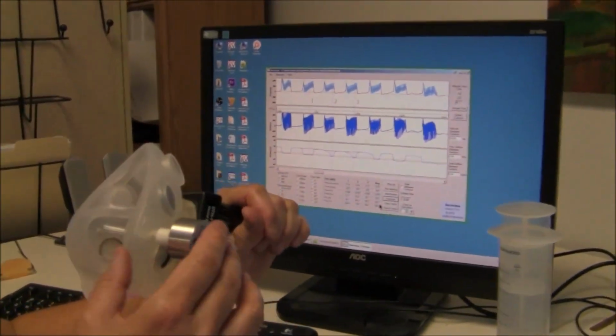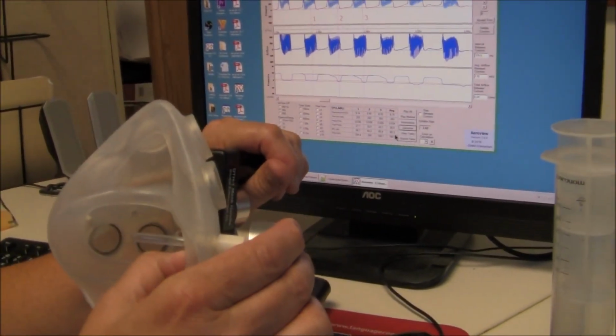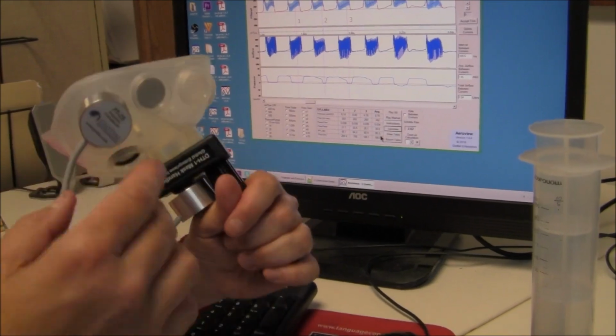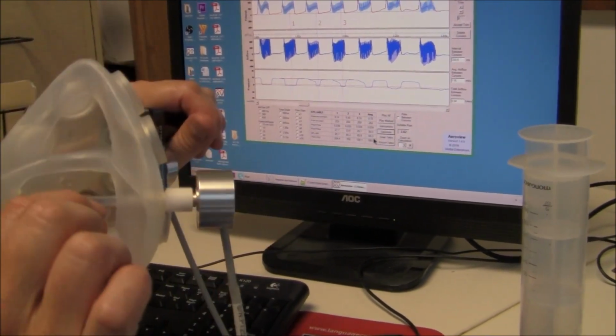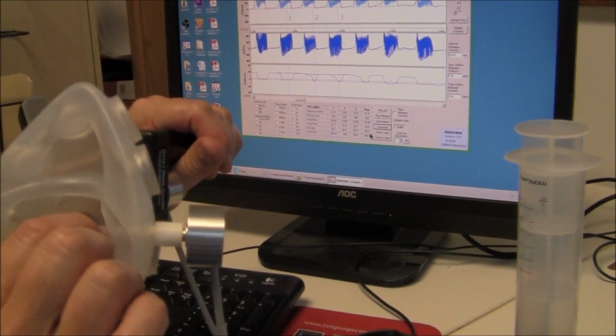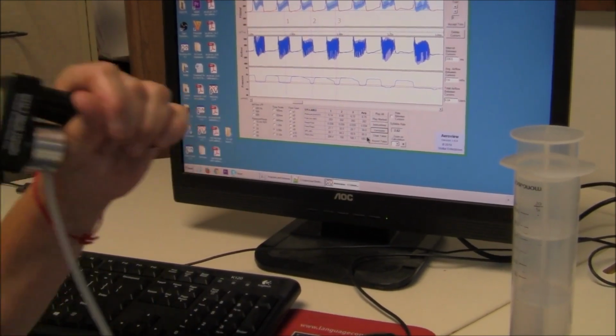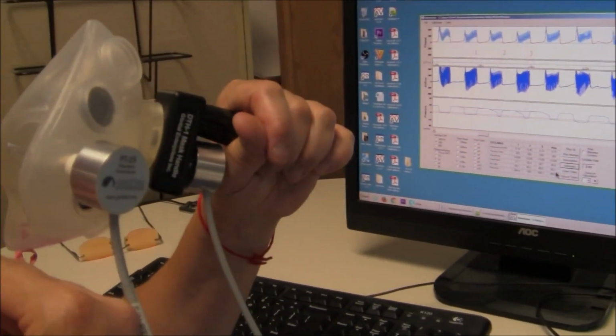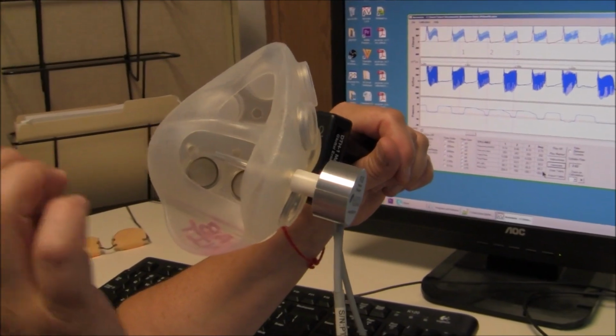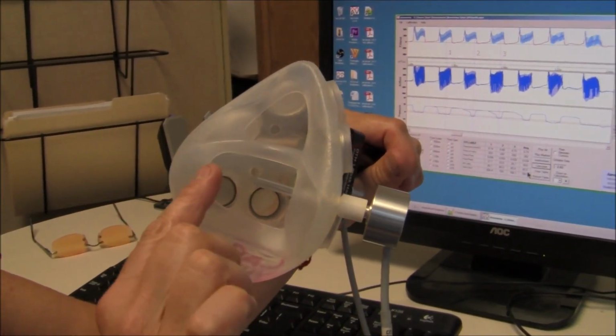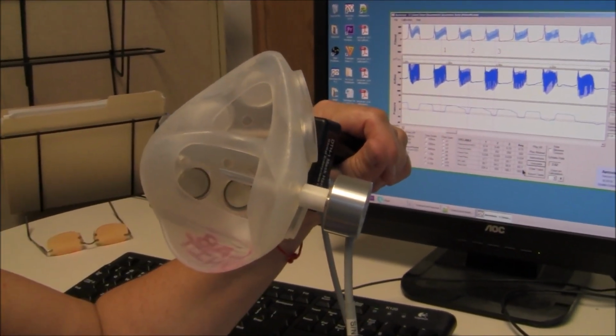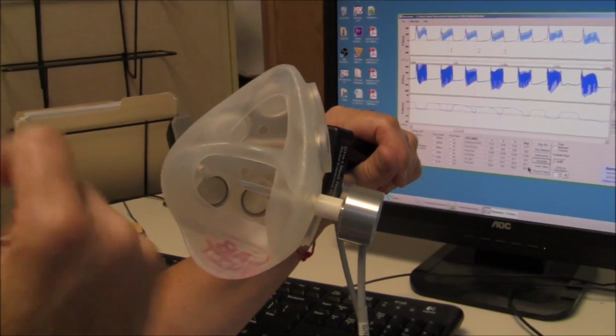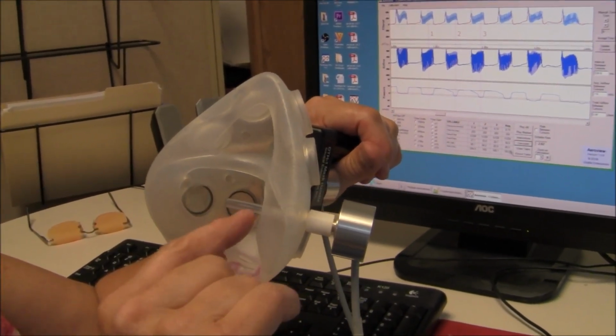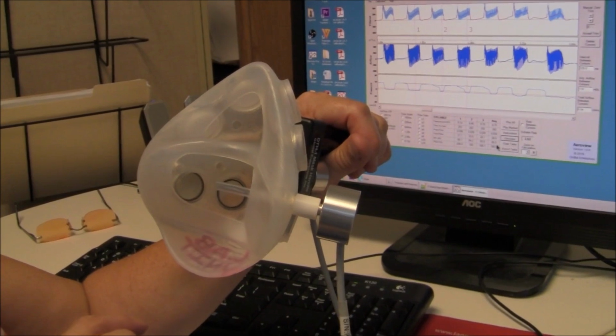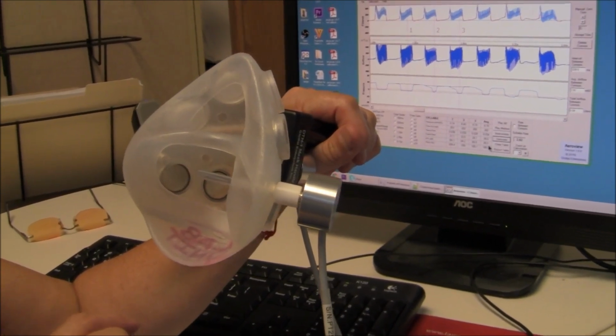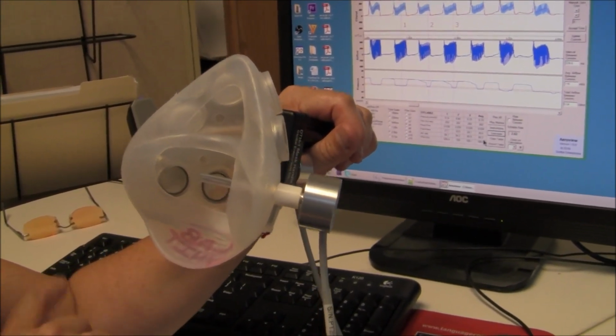I wanted to add that when measuring pressure using the PT25, this is the tube that we supply you, and it's very important that your tongue, when you're vocalizing, is not blocking the tube. So it should go in the corner of the mouth and out of the way of the tongue. If you need to, you can cut this shorter. But you may have to do some experimenting until you get a good pressure pulse.